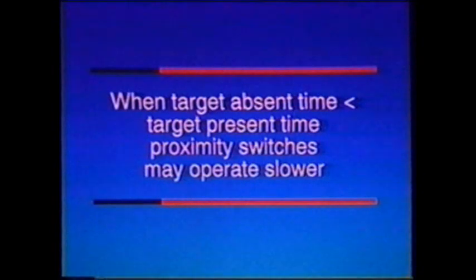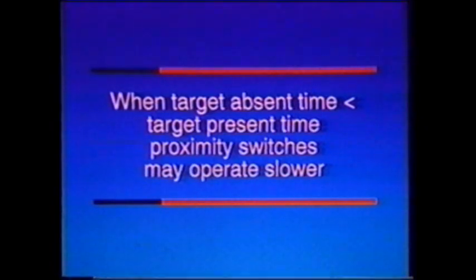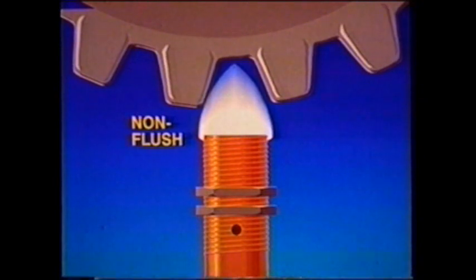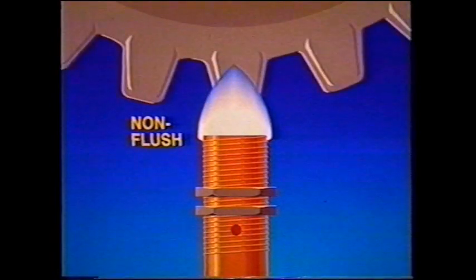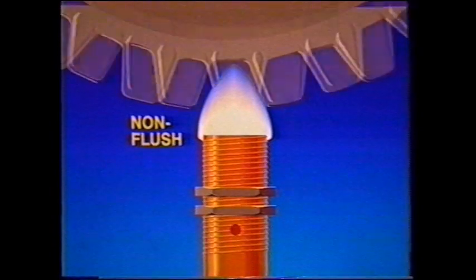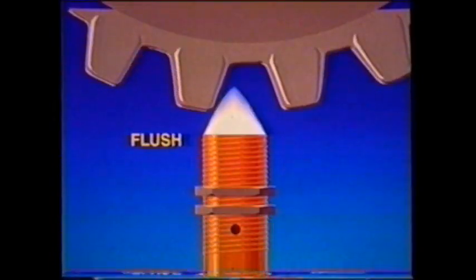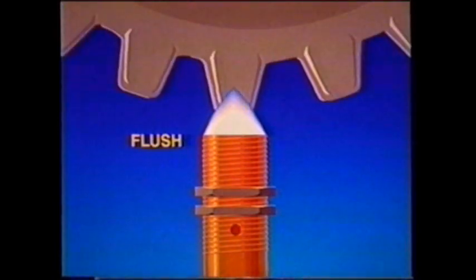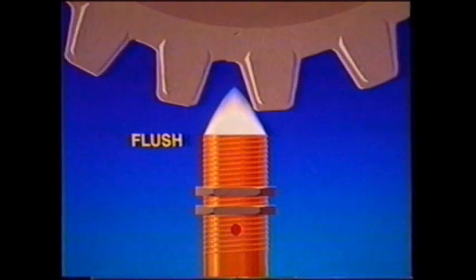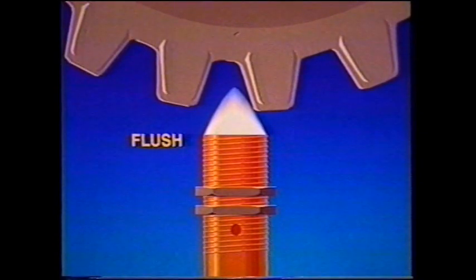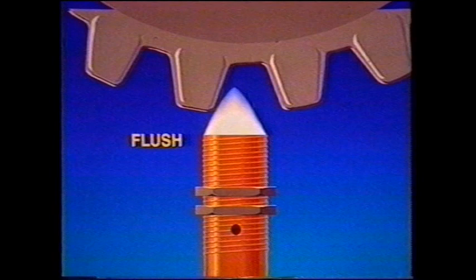The most difficult applications are rapidly moving repetitive targets with a small space between them. One common example is counting gear teeth using a non-flush switch — as a tooth leaves the active zone, the next tooth is about to enter, and chances are the switch will not have enough time to turn off. Using a flush switch in the same application, when the tooth leaves the zone, there is more time until the next tooth arrives because the zone is narrower, and the switch will probably have enough time to turn off. So if turn-off delay could be a problem, use a flush switch.